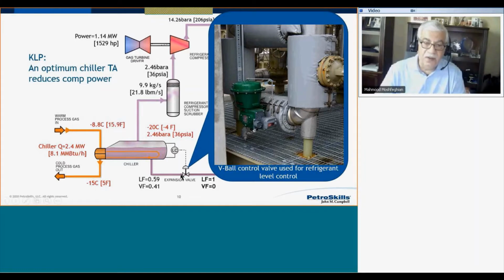As we cool down, or as we reduce the pressure, because the chiller pressure, as you can see here, is low, and chiller pressure is dictated by chiller temperature. There is a direct relationship between temperature and pressure for a pure component. So we drop the pressure from 200 psi to say 36 psi. Temperature goes down to -4 degrees Fahrenheit as we desire. But look at the liquid fraction. At the inlet, liquid fraction is 1, but at the outlet of the valve it is only 59% liquid and 41% vapor.